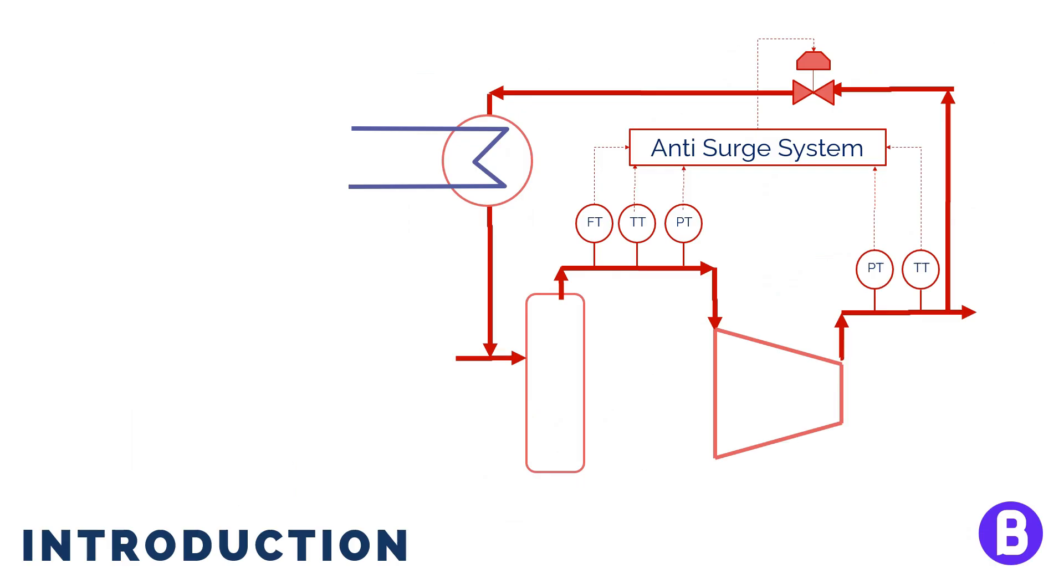Or in case of a compressor, we may need a hot bypass line during startup in case we are afraid of surge scenario. The surge scenario, anti-surge protection, and the need for a hot bypass line is usually studied by the compressor's manufacturer.